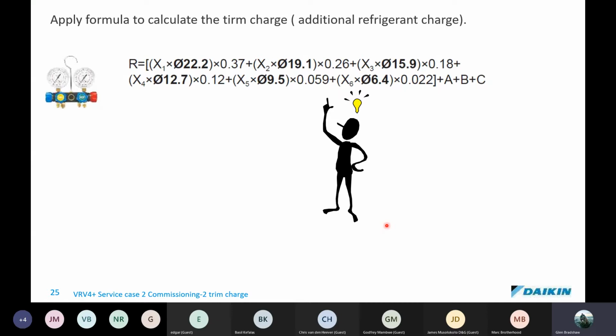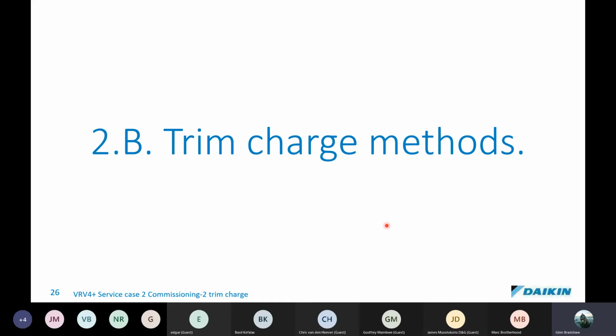And remember, right back in the planning stages of our installation, I said to you guys, when you've got a schematic diagram, work on that schematic and daily update the lengths of piping on it. Don't try and do it at the end when people have closed up the ceiling and now you've got to do a whole lot of guesswork. It's critical that we get the exact amount, regardless of which of the trim methods you're going to use when charging up the system. So let's have a look at those trim methods.